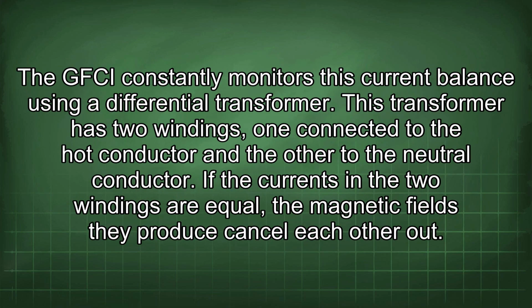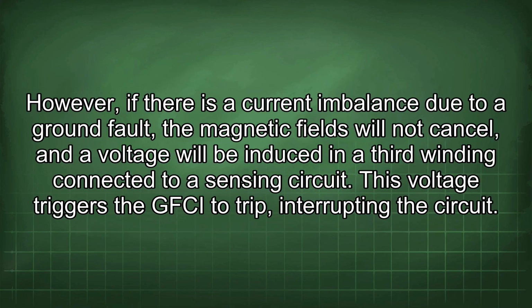The GFCI constantly monitors this current balance using a differential transformer. This transformer has two windings, one connected to the hot conductor and the other to the neutral conductor. If the currents in the two windings are equal, the magnetic fields they produce cancel each other out. However, if there is a current imbalance due to a ground fault, the magnetic fields will not cancel, and a voltage will be induced in the third winding connected to a sensing circuit. This voltage triggers the GFCI to trip, interrupting the circuit.